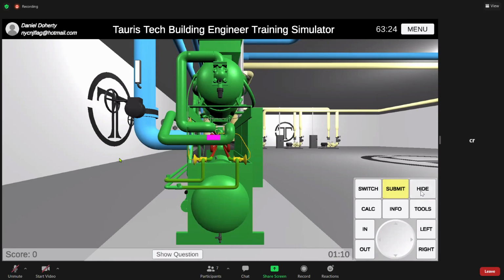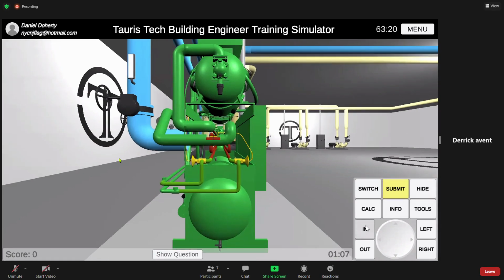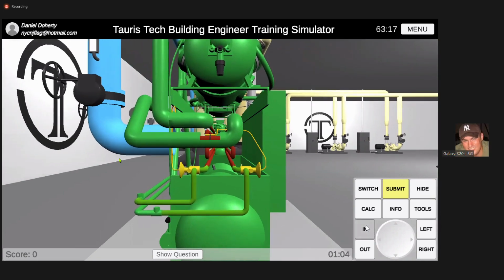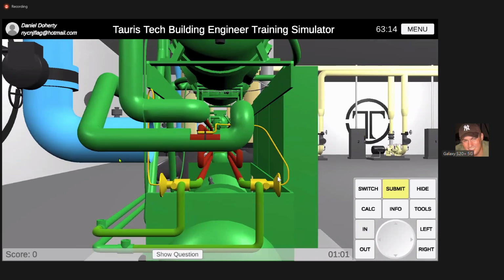So what does the sensor bulb do? It opens and closes that diaphragm. There's a diaphragm on top of this TXV. Okay? And there's liquid inside this line, and there's liquid inside the sensing bulb. So what happens is when the refrigerant turns from a liquid to a vapor because it boils off in there, it creates pressure, and that creates a downward pressure on the diaphragm, and that pushes the diaphragm down. On the other side of the diaphragm is a spring, and that decides how much refrigerant goes into the evaporator. Okay, got it? Got it.